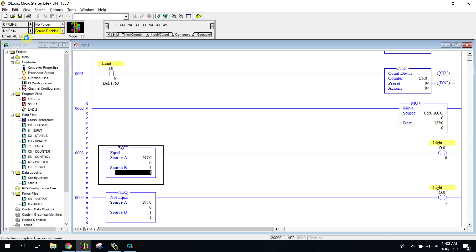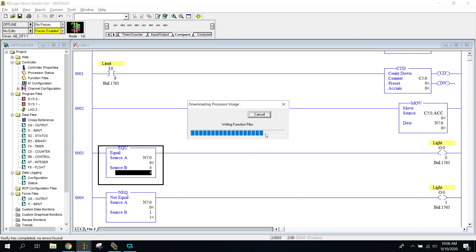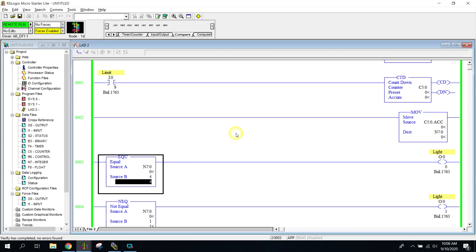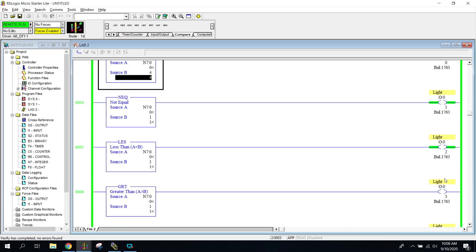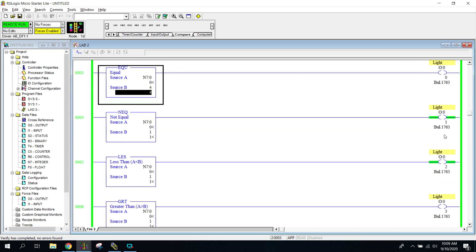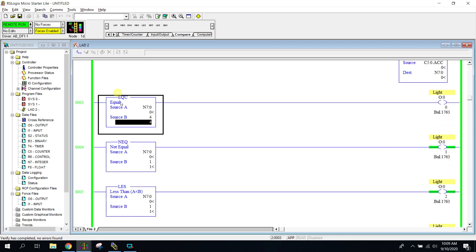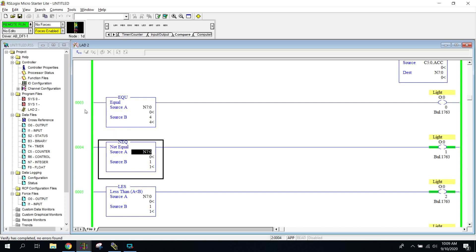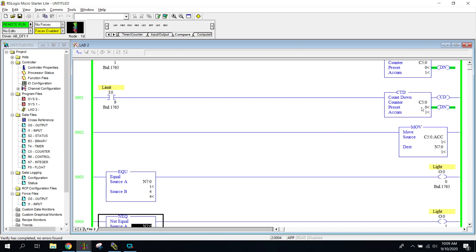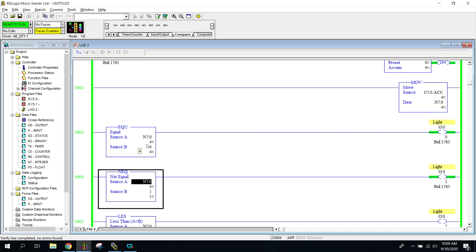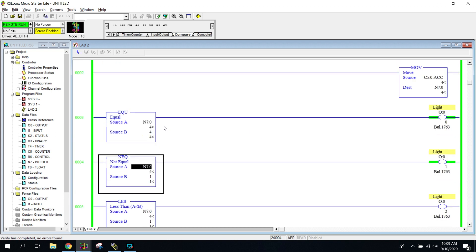Let's go ahead and download this. Now most of these are hooked up to lights — some are actually contactors, so you might hear them in the background. This very first one on rung three is comparing source A to source B to see if they are equal. I'm going to count up the counter — source A now equals four, source B is four, and it creates a path of true, turning on my light. Very simple. This could represent five trucks in a loading dock being counted up to start a filling program.